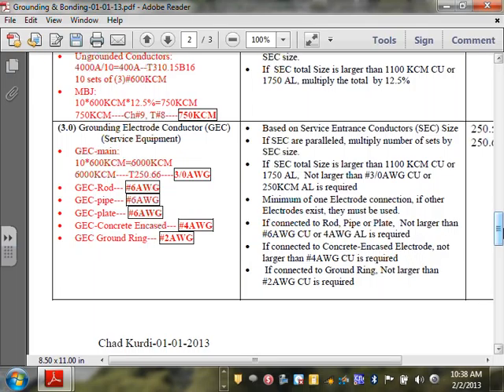So there are studies, and that book goes through it, guys. Now we're getting to the detail here. There are studies that say the further the voltage drop. Remember that voltage drop on the feeders? You have to apply the same voltage drop rules on the grounding, the equipment grounding conductor and the grounding electrode conductor. So long story short, if it's too long, the impedance of the cables might be high enough that it will not allow the overcurrent protection device to operate fast enough to trip you on a ground fault. This will be a ground fault. So that's how they always go in that one, higher.